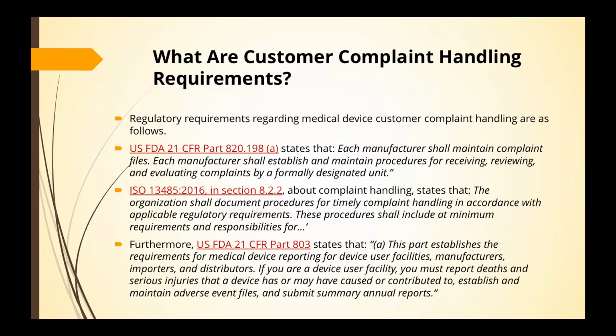Similarly, for ISO 13485, in clause 8, section 8.2, there is also a requirement saying the organization shall document procedures for timely complaint handling in accordance with applicable regulatory requirements. These procedures shall include, at a minimum, requirements and responsibilities for the manufacturer, and so on. So they are also asking for the same thing, that there should be SOPs and work instructions in place which are timely and compliant for complaint handling. So this is for the 13485 requirement.